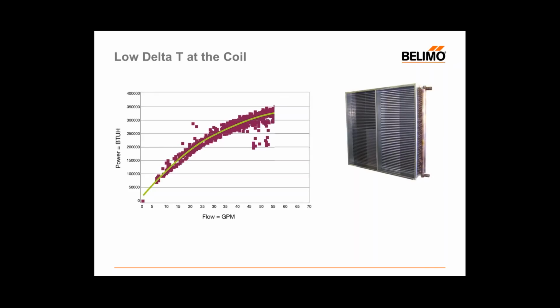And if you think about how a coil is designed, or how it functions rather, this actually makes pretty good sense. A coil's a long piece of copper tube essentially, and we're going to take some really cold water in this case, as it's a chilled water coil, and if we put it through that coil really slowly, each molecule of water takes a long time to pass all the way through the coil and come out the other side. And so it has a substantially longer period of time in which it could exchange its heat.